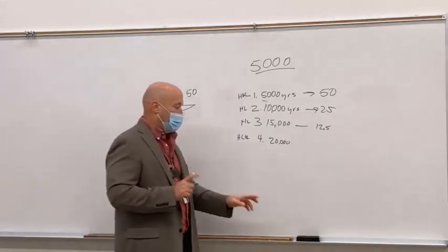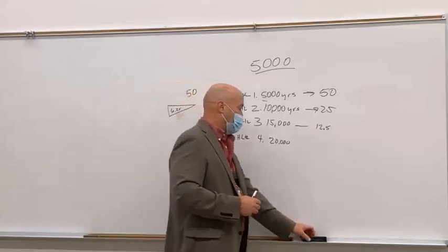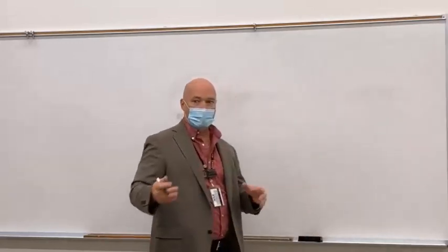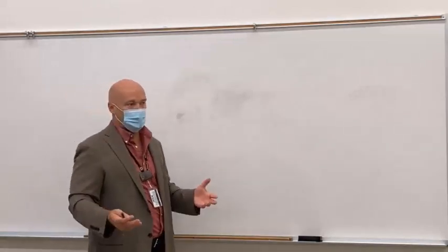Okay, so in X-ray, we're not dealing with radioactivity. What we're dealing with is just electromagnetic energy. And in X-ray, we measure the quality of the X-ray beam in half-value layer. So half-life is radioactivity. The equivalent in X-ray is half-value layer. The half-value layer is where we use some sort of absorber, and the most common is aluminum because it's readily available, and it's what we use for filtration anyway.